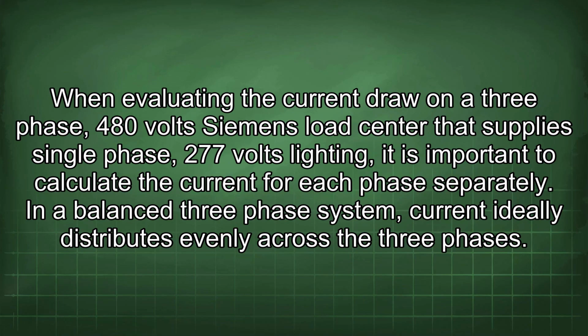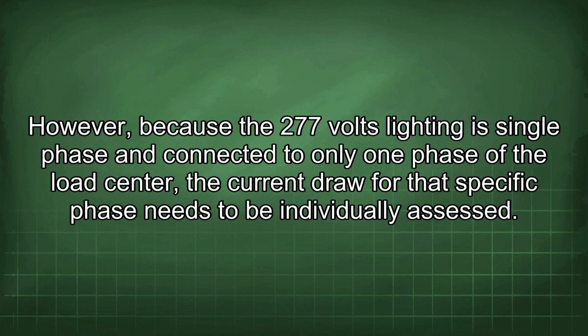When evaluating the current draw on a three-phase 480 volt Siemens load center that supplies single-phase 277 volts lighting, it is important to calculate the current for each phase separately. In a balanced three-phase system, current ideally distributes evenly across the three phases. However, because the 277 volts lighting is single-phase and connected to only one phase of the load center, the current draw for the specific phase needs to be individually assessed.